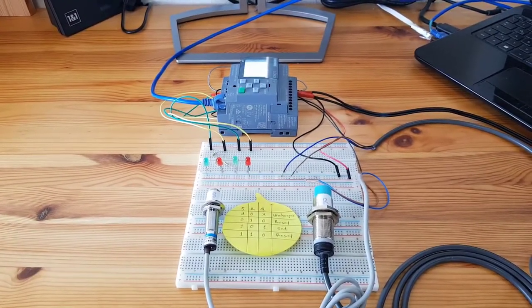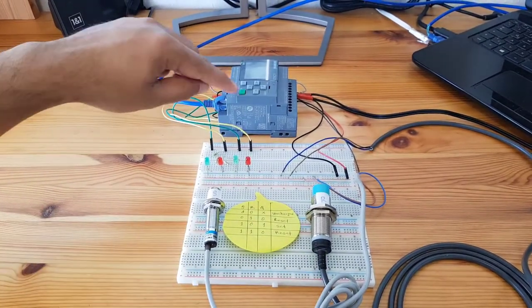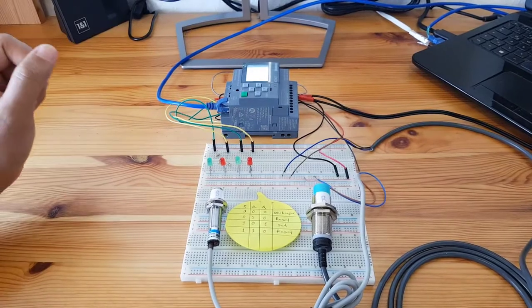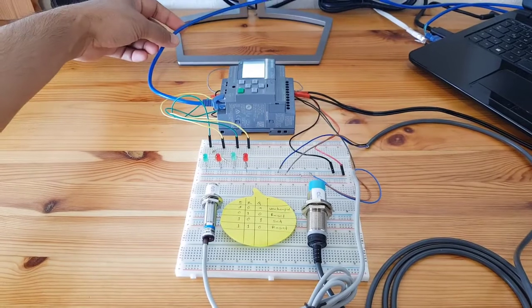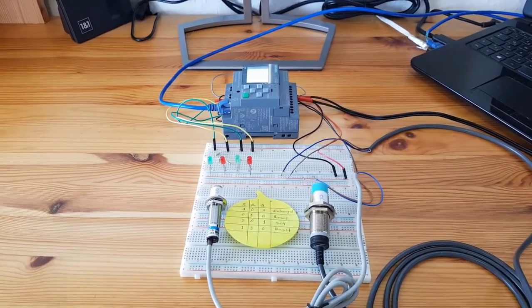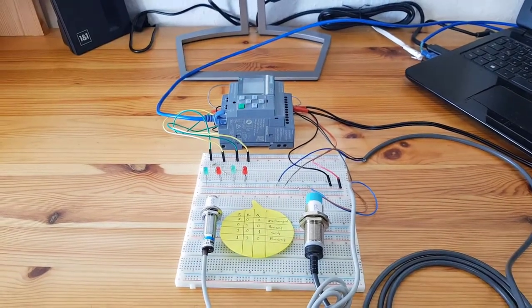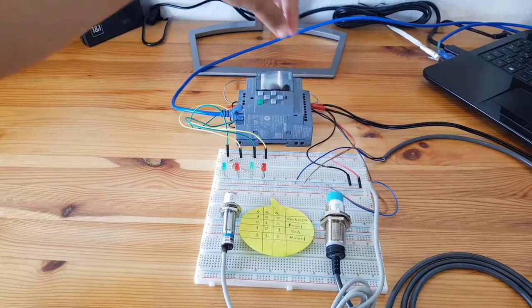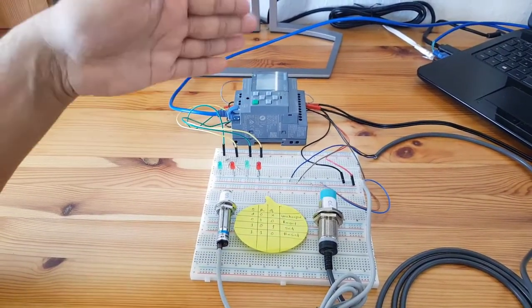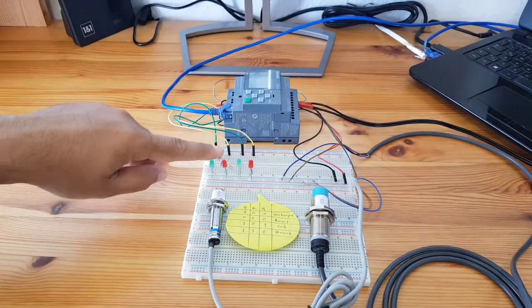Now I'm going to show you the practical use of the latching relay function using two inductive sensors and the LOGO PLC. Here you can see two inductive proximity sensors and one LOGO PLC — it's the LOGO 8 model. One advantage of this PLC is that you don't need any programming cable, just one LAN cable. The PLC has inputs I1 through I8. I've connected two PNP NO-type inductive proximity sensors as inputs, and for the output I'm using an LED — you can use any actuator depending on your application.